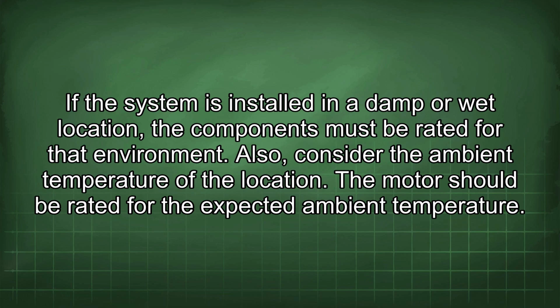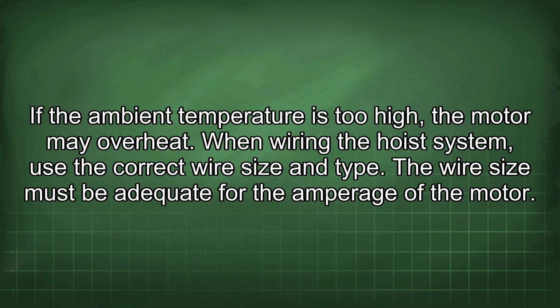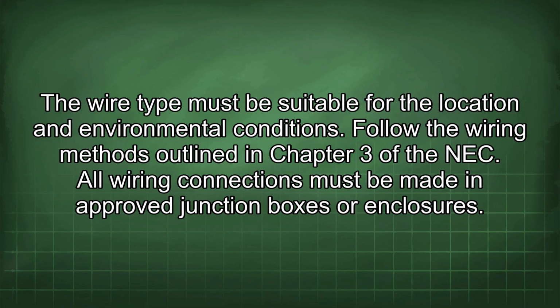Also, consider the ambient temperature of the location. The motor should be rated for the expected ambient temperature. If the ambient temperature is too high, the motor may overheat. When wiring the hoist system, use the correct wire size and type. The wire size must be adequate for the amperage of the motor. The wire type must be suitable for the location and environmental conditions. Follow the wiring methods outlined in Chapter 3 of the NEC.